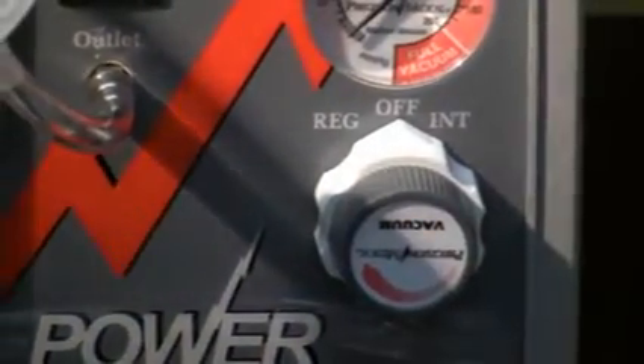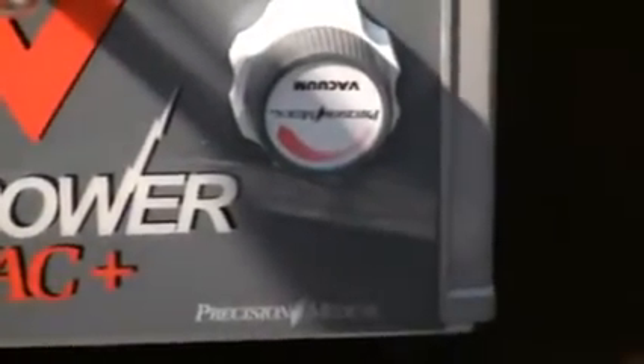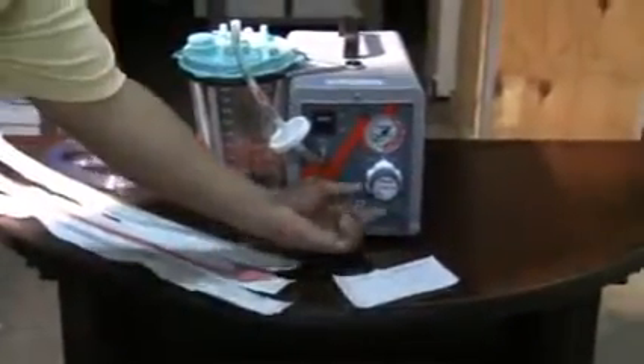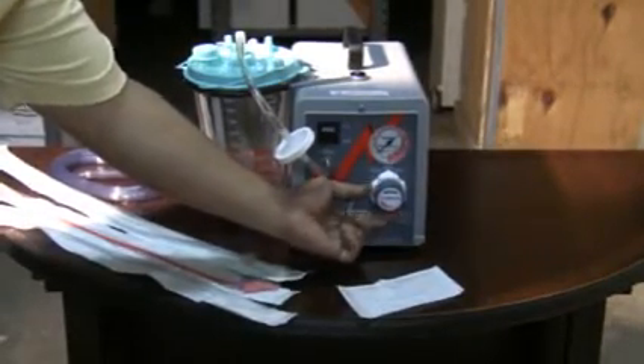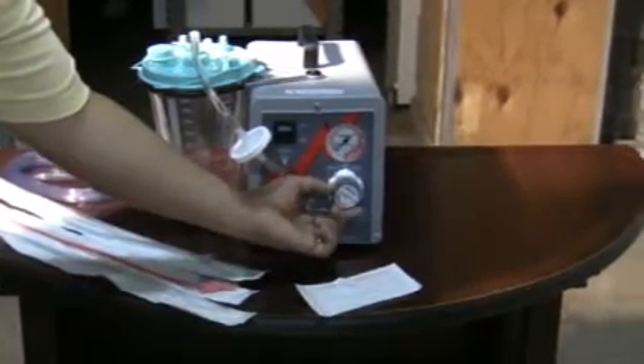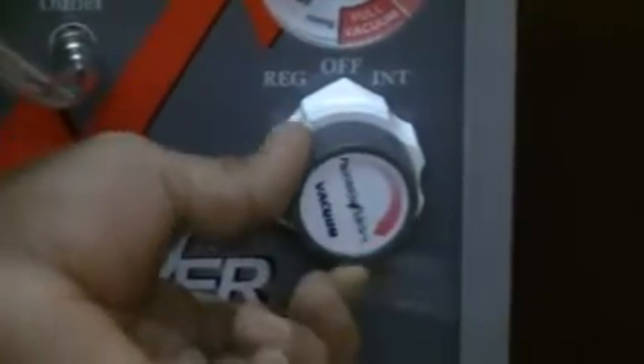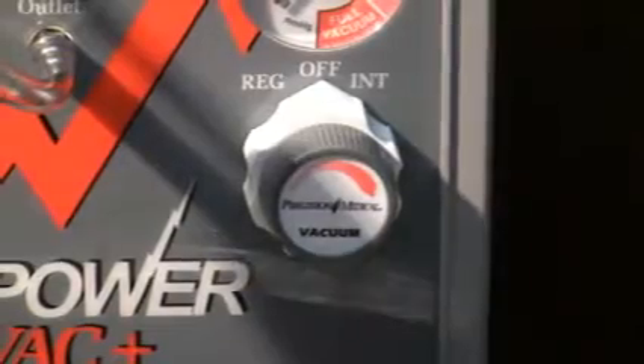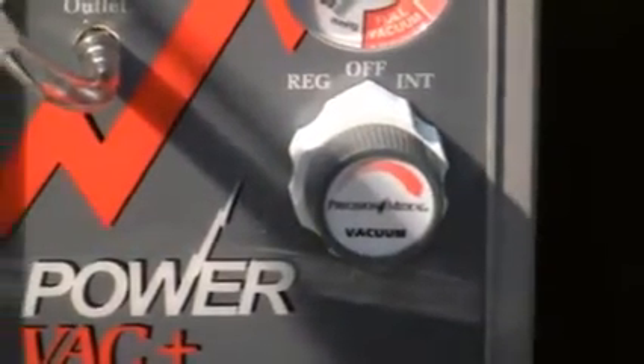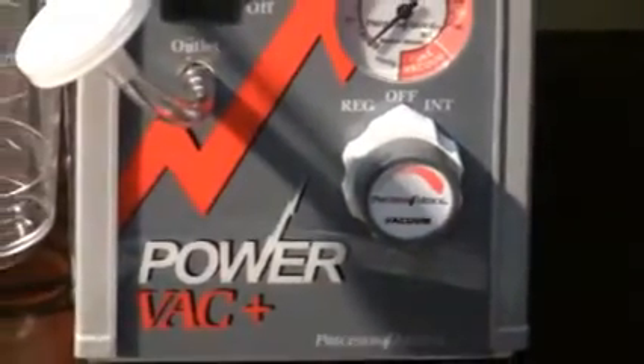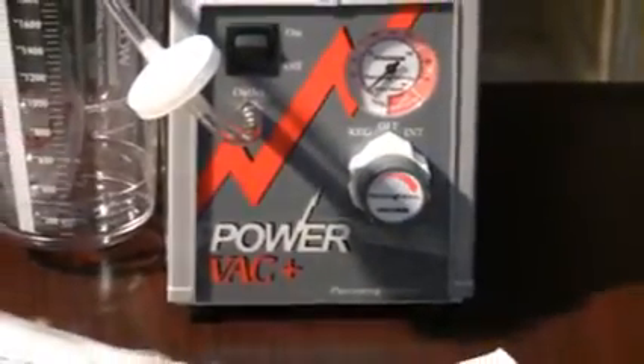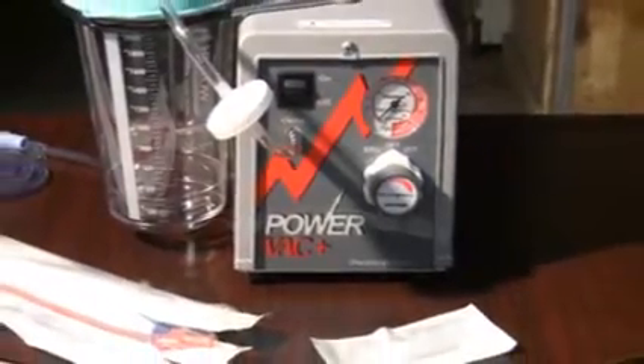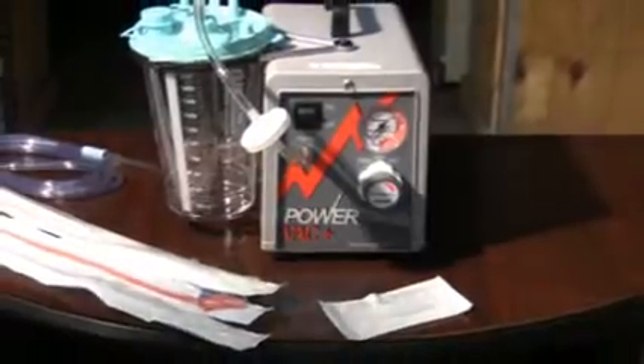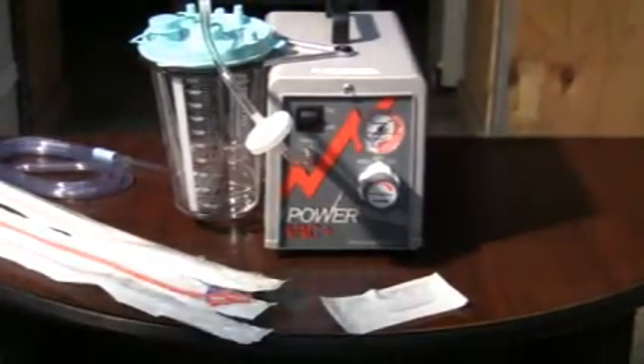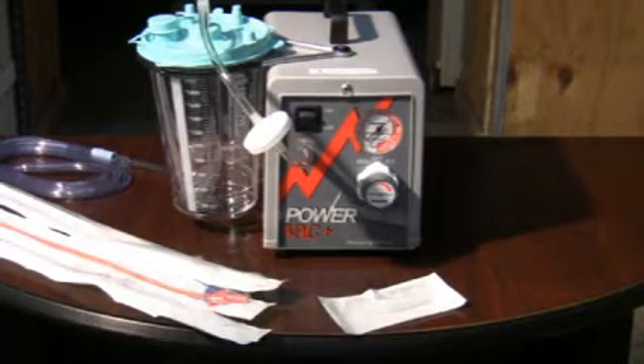When it is selected in the REG position, it will be continuous vacuum pressure that will be adjustable with your vacuum adjust knob. Your vacuum adjust knob is directly located in front of your vacuum mode selector. This vacuum pressure knob is gray in color, and to increase your vacuum pressure it should be turned to the right, clockwise, and to decrease your vacuum pressure it should be turned to the left, counterclockwise. The vacuum pressure should always be predetermined by the physician. For the safety of the patient, it is generally recommended to always start with smaller amounts of vacuum and then increase the vacuum pressure as needed so you can get the obstruction cleared.